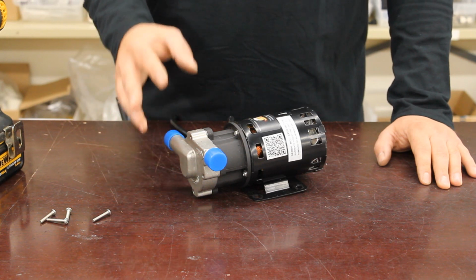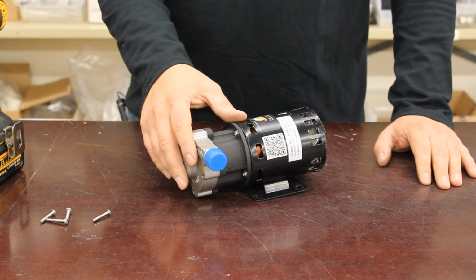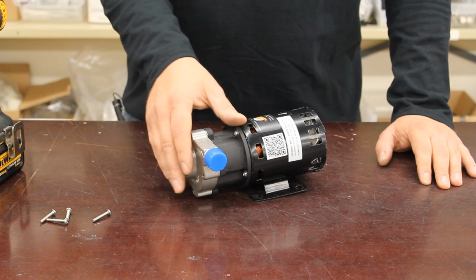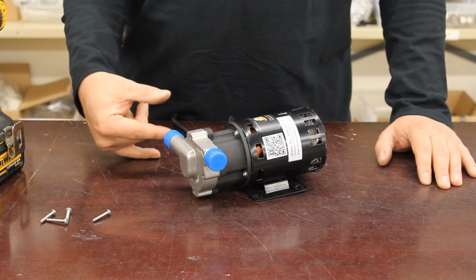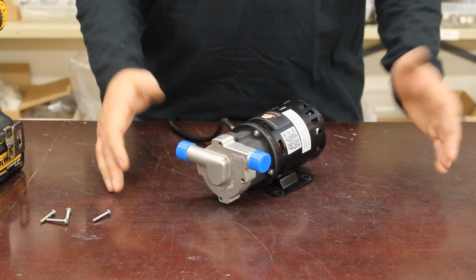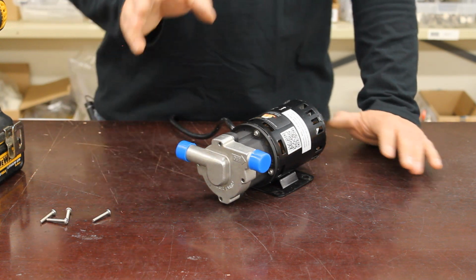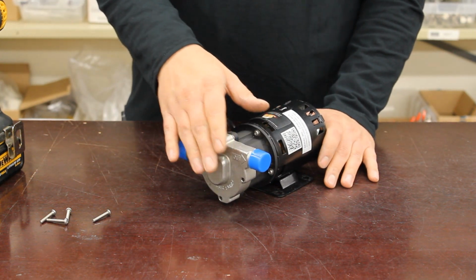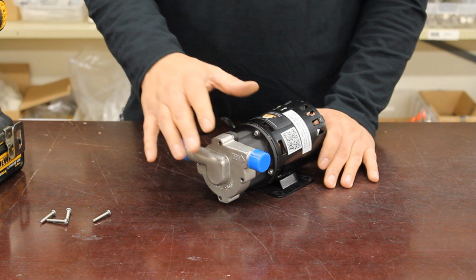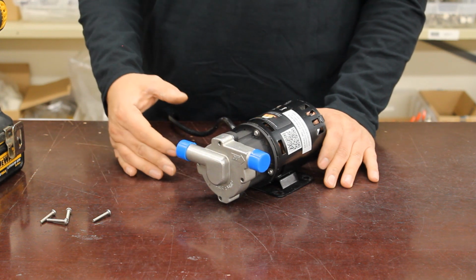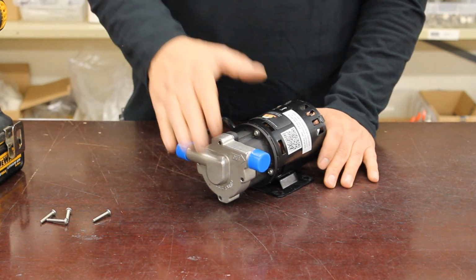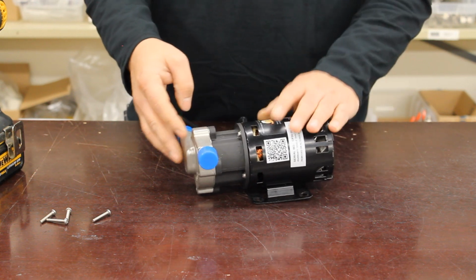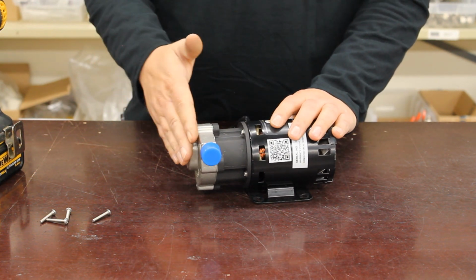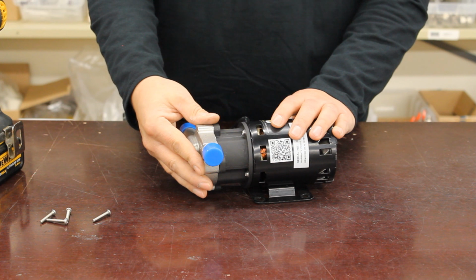So priming the pump means flooding the head with liquid such that there is no air in the head itself or in the line leading to the pump input. Bottom line, these pumps are not self-priming. So if you're absolutely positive that the pump head is flooded and there's no air in the line leading up to it, then you may have condition number 2, which is that something is fouled inside the head itself.